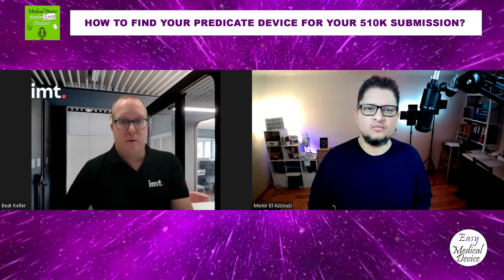I mean, in the end, if we don't have a predicate device, then you would need to go the PMA or de novo path. And what is important in this case? Explain what you need or what you want to do, and create a pre-submission. Don't just file de novo. Don't just file a PMA. It's too expensive. Just write down what you want to know from the FDA. Create a pre-submission. Within some weeks, you get an answer. You can even sit together via video call or telephone call with the FDA and discuss your questions.